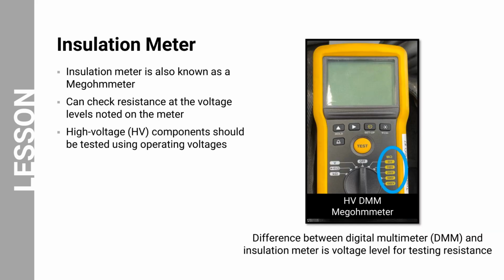Insulation meters, also known as megohmmeters, play a vital role in isolation fault testing as they measure electrical resistance, particularly at high voltages compared to a standard digital multimeter, abbreviated as DMM. The high voltage capability allows an insulation meter to evaluate the integrity of insulation in high-voltage systems, where even small leakage currents can be dangerous. The meter can be set to various voltage levels depending on the specific component or system being tested. While a digital multimeter can measure resistance, its voltage output is typically limited to low ranges, under 1,000 volts. This makes it unsuitable for testing high-voltage components where leakage currents are of concern.